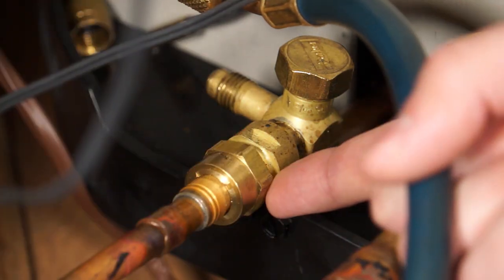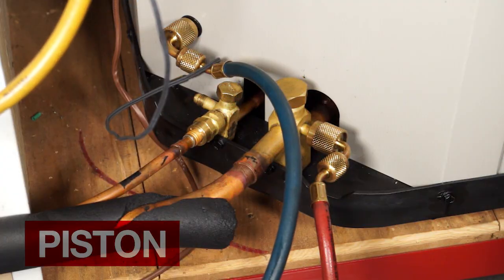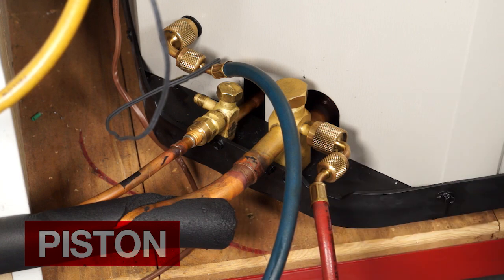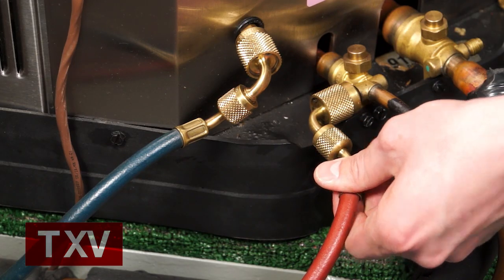Determine if your system has a piston or a TXV, place your blue hose on the common suction port. On a piston system, place your red hose on the large copper line. On a TXV driven system, place your red hose on the liquid line.